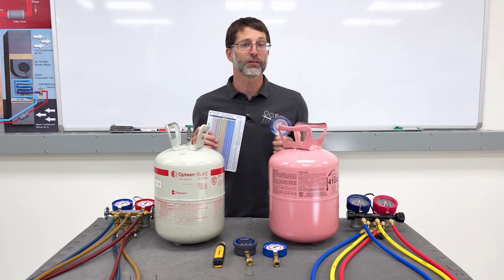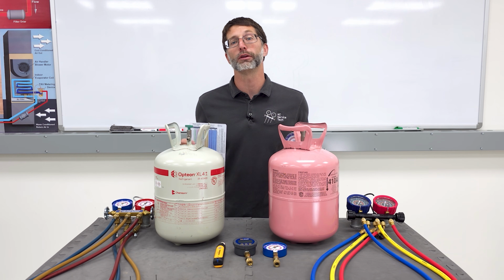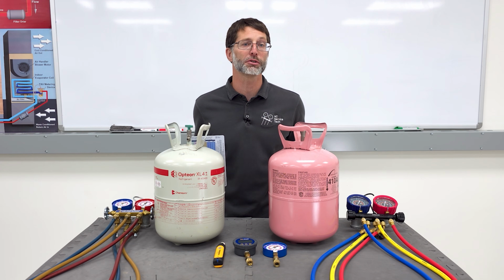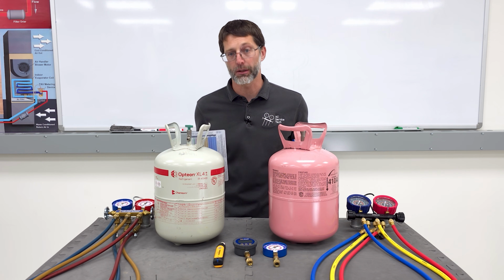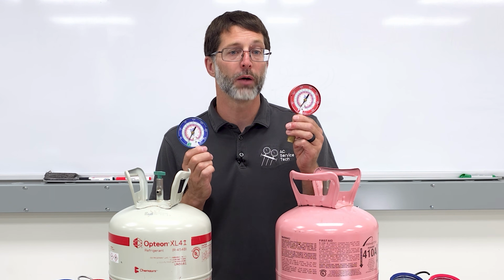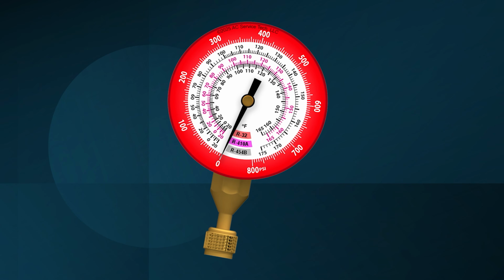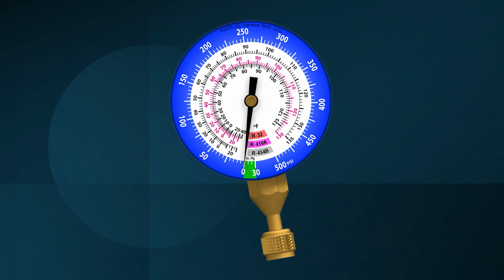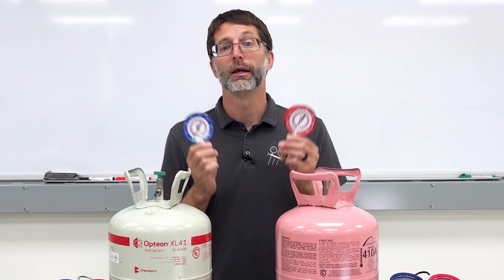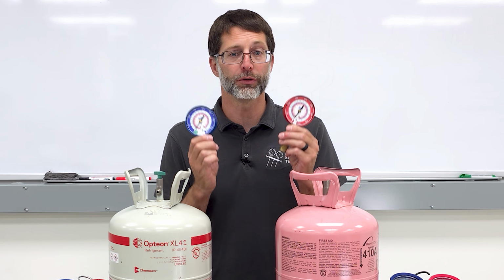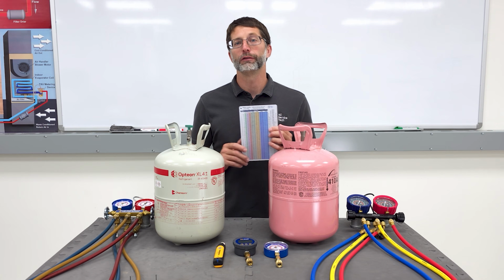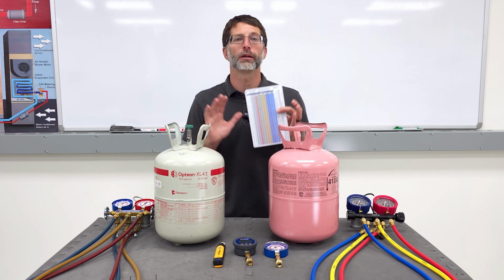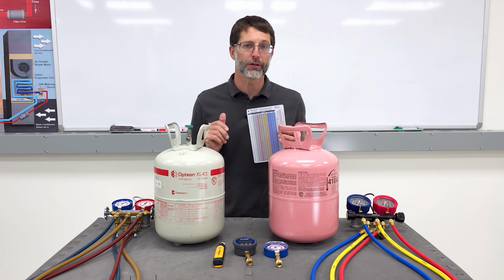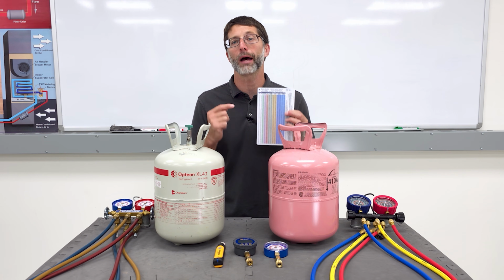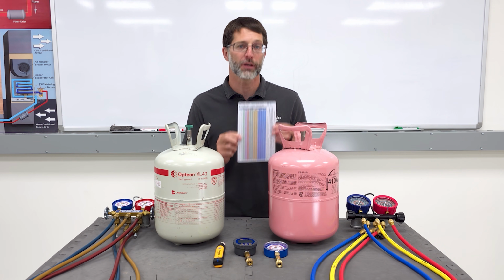Compound manifold gauge sets meant for heat pumps may come with 2 high pressure gauges used for measuring high pressures during heating mode. Gauge stubs may also come with either a high pressure red gauge or a low pressure blue gauge. See figure 4-29. Gauge stubs avoid the need for hoses in order to connect to a system. If a gauge face is connected to a system that contains a refrigerant not listed on the gauge face, then a separate PT chart or app must be used to determine the saturated temperature.